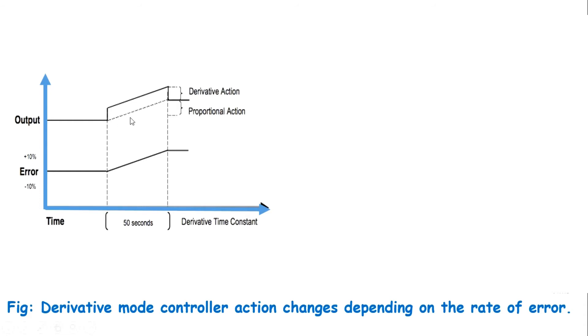This line shows a proportional controller due to a process variable error from set point. Using derivative that is shown by solid line, the control output jumps up, rises in a ramp and then falls back to proportional control action when the error becomes constant.